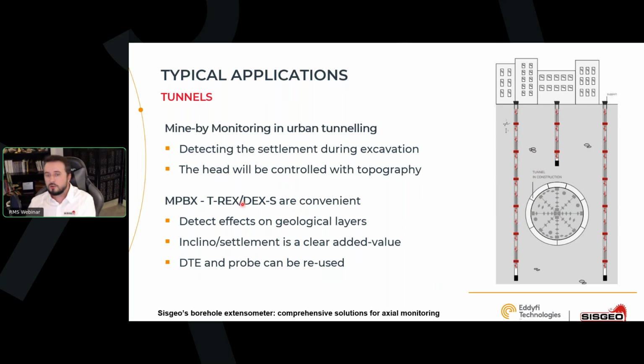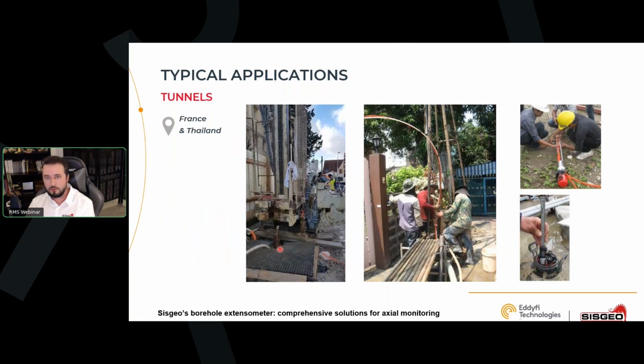And here you can also combine the T-Rex/DEX-S with an inclinometer. So it's a clear added value in order to have only one borehole with all the information. And the advantage also is that the electrical transducer or the probe can be reused. So here you can save some budget on it. Some examples here in Thailand and in France, where we were dealing with monitoring some subway projects. So the extensometers are pre-equipped inside the boreholes.